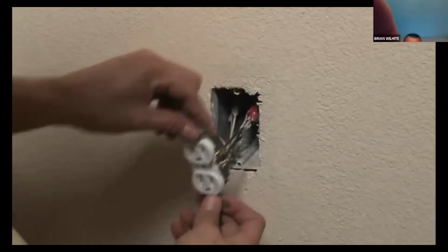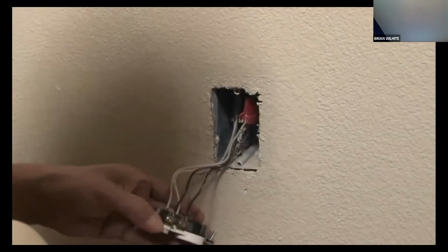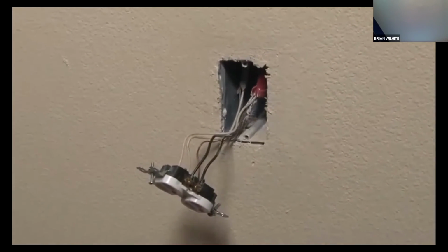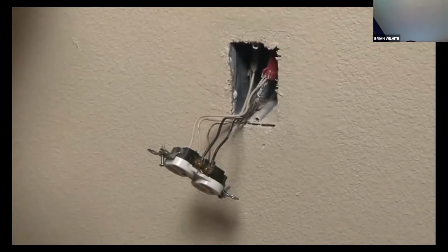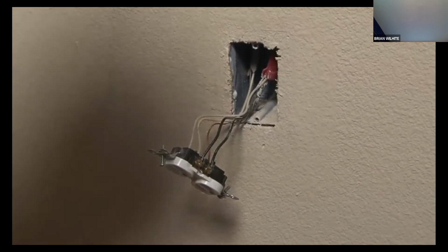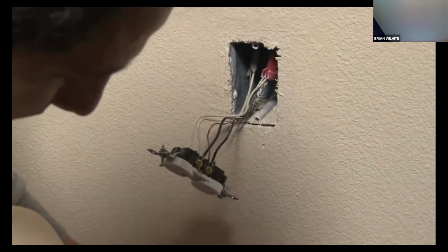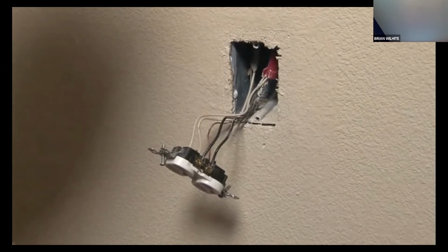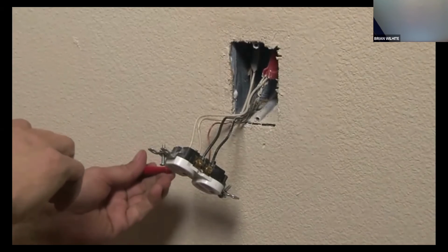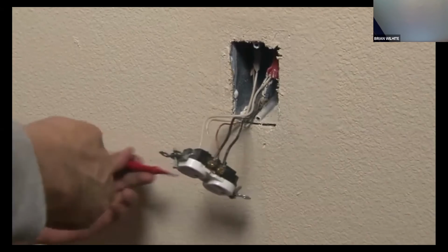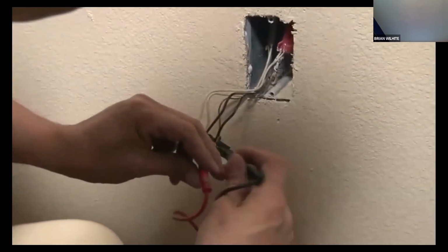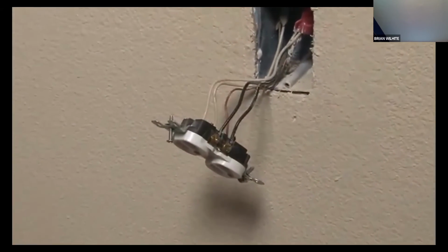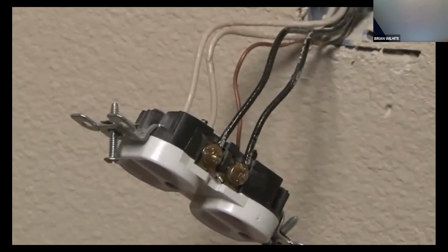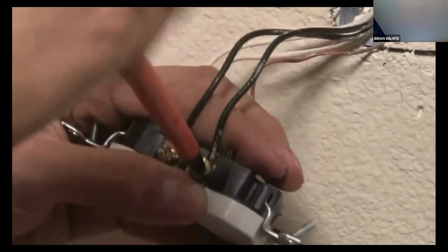He's now going to pull the outlet out for inspection, and he's going to check it for continuity. He's going to use his multimeter and check the outlet to find out what the problem is. He checks the neutral, he checks the black wires coming in, and he finds no continuity on the black wire. So it's determined that there is a short in the outlet and it needs to be replaced.